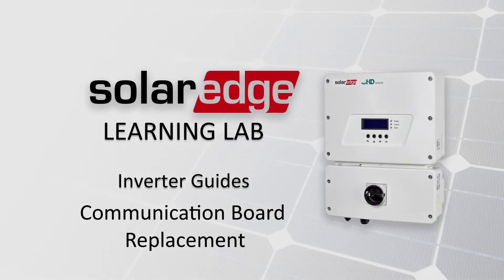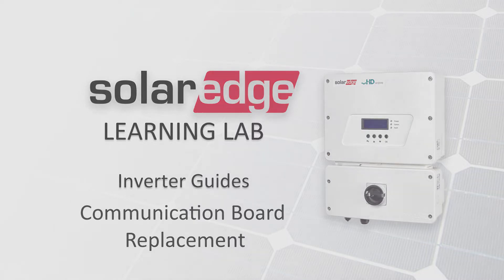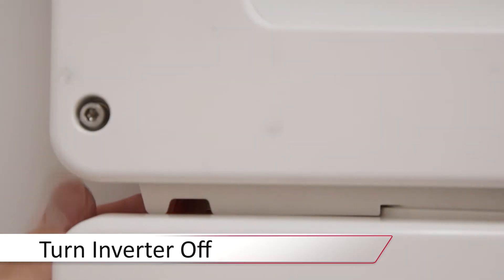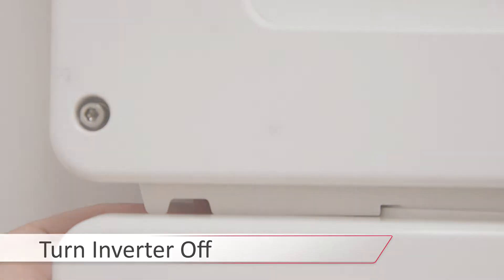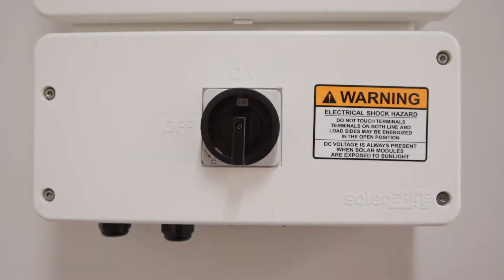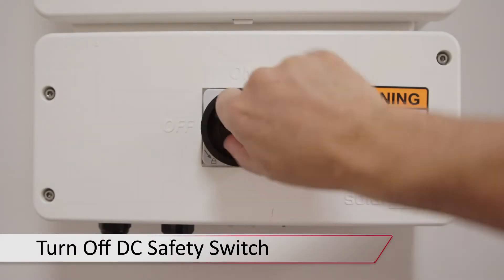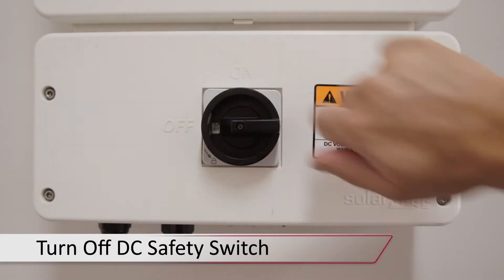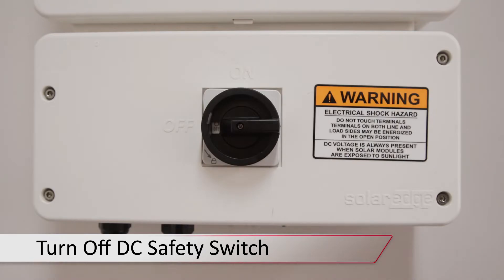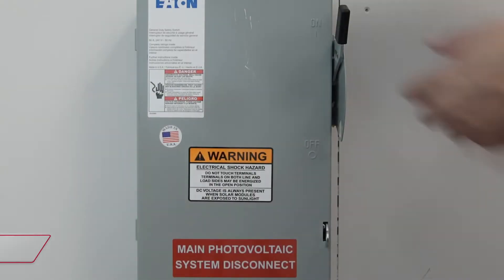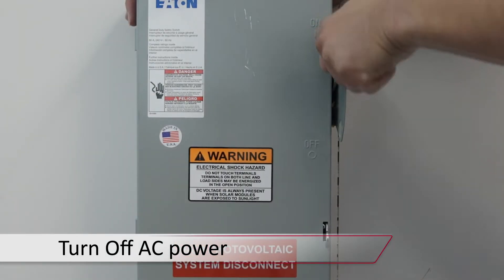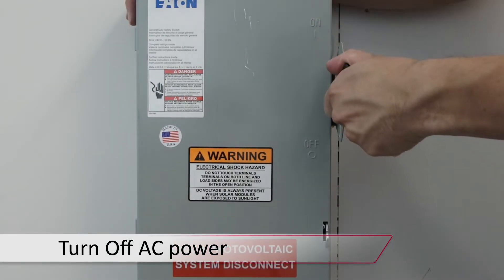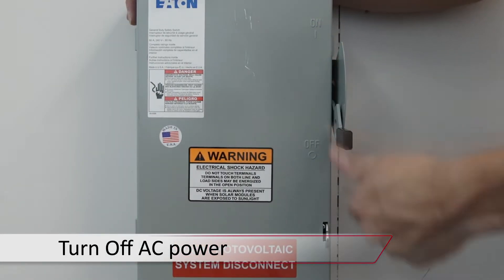Prior to beginning work, always ensure that the system is de-energized. Turn the inverter on-off switch to the off position. Allow the DC voltage to bleed down below 50 volts DC, and then turn off the DC safety switch. Turn off AC to the unit and remove the top cover.